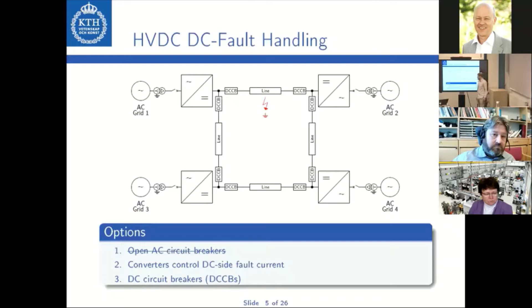And if one would use option 2, this would entail that the DC voltage of the whole HVDC grid is ramped down, and hence the power outages would also be very high and potentially unacceptable. If the grid is further expanded to, for instance, a mesh configuration, option 2 really is unacceptable, and the only option are DC circuit breakers. And this is why we have considered them in our research.